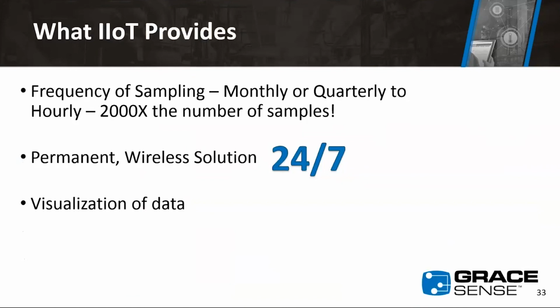The big thing IoT provides in general is the frequency of sampling. In a top class facility you might have monthly vibration captures on your critical motors, more often quarterly or sometimes not even that. But when we take hourly samples, we get 2,000 times the number of samples than if done monthly, so it's a wealth of information we can capture to provide a history of what's going on with the equipment.